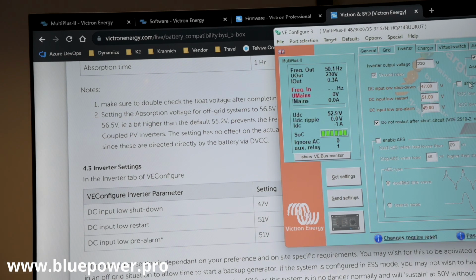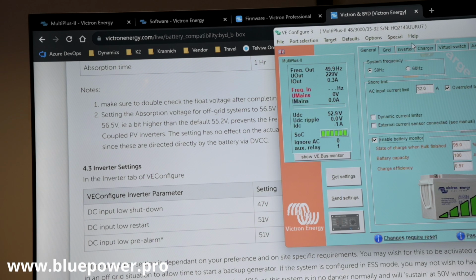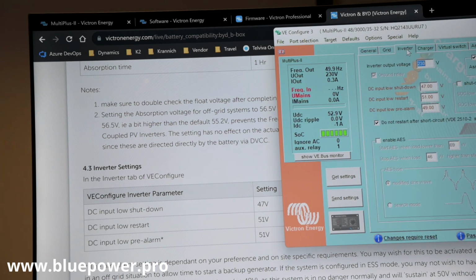Then here on the side, we've got shutdown on SOC, but that's going to be as accurate as the settings over here. And the battery capacity. Some batteries will have 101 amp hours, and over a long period of time that drifts, so you're going to end up having your battery at 100%, but the Victron is going to think it is at 95% or whichever. So it's not too reliable, unless you've got a GX device, then you can activate that, because the GX device synchronizes the battery BMS SoC with the inverter.